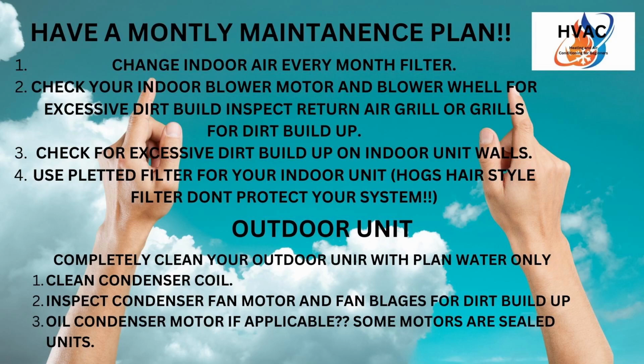Then go ahead and do some inspection. First thing I would do is look all the way around and see how dirty it is. Sometimes you might have to undo the 5/16 screws that hold the top, and without pulling the wires out, you can lift that up and prop a piece of 2x4 in there to keep it up. That allows you to get to the inside of the coil as well as the outside of the coil. You can start from the inside and wash it all the way down, and that'll let you see if your spray is pushing through.